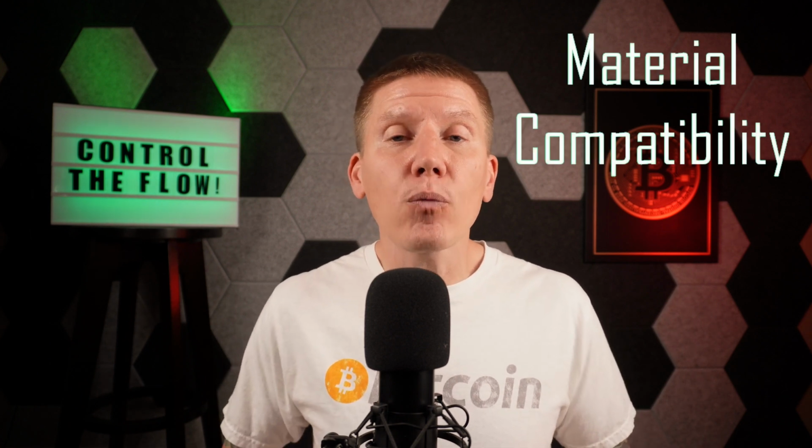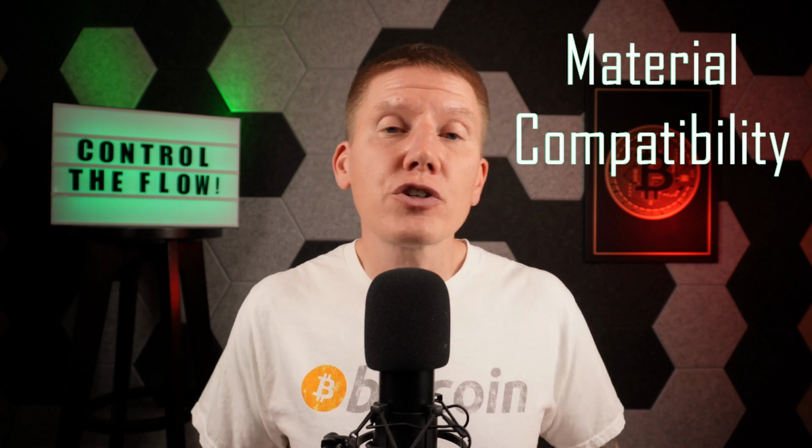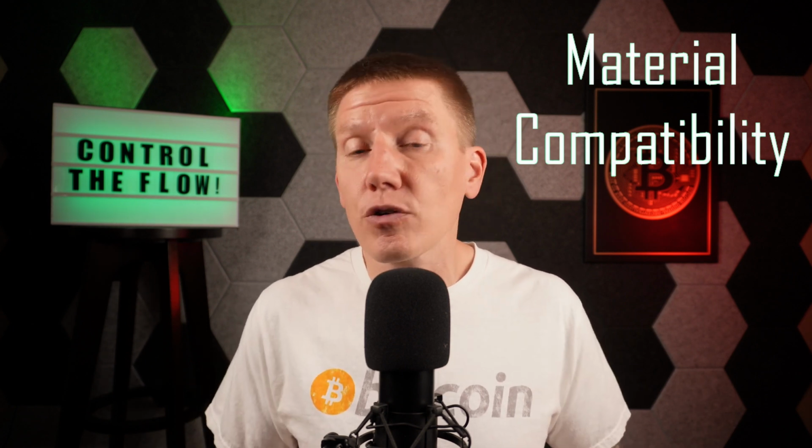Now, one last point to be aware of here is that all these pumps are designed for cooling loops using water or water glycol mixtures. None of these pumps are designed with Bitcoin or miner dielectric fluid in mind. So before you pick out your pump, get a hold of the manufacturer's data to understand what the internal components of the pump are and what it's made of. If you can, find a pump with most, if not all, of its internal components on your fluid's material compatibility list.